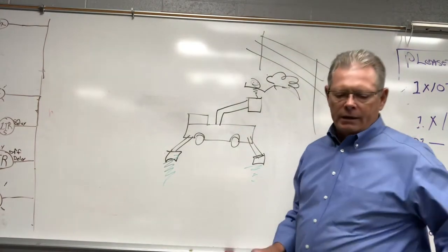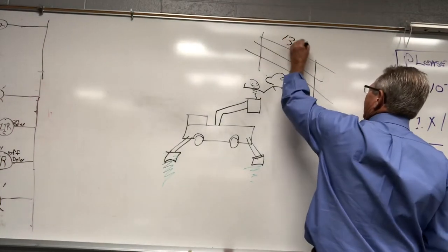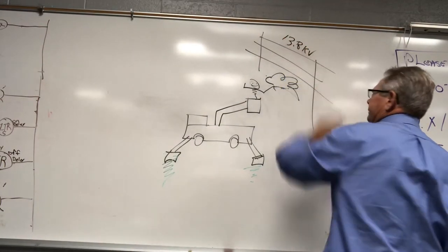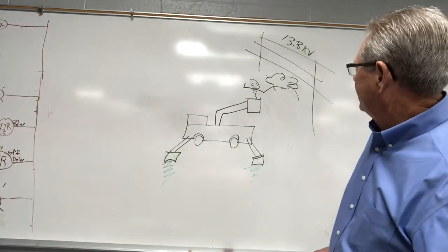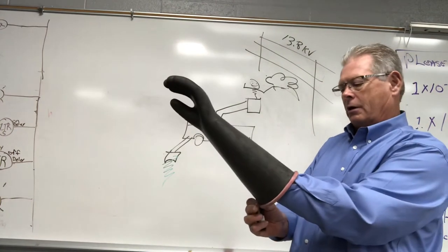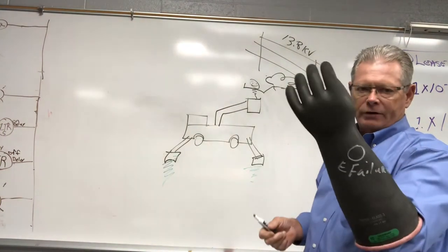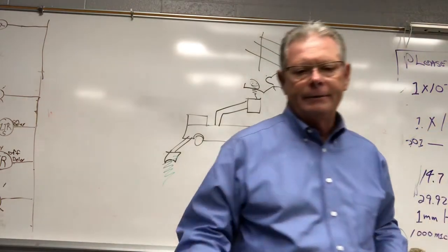Now let's say he's working on a 13.8 kV line, might be what goes in front of your house. So the gloves would be much like these because these are 26,500 volt gloves. They're tested for that, how they do that, you send them off.